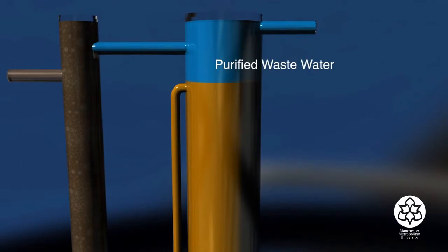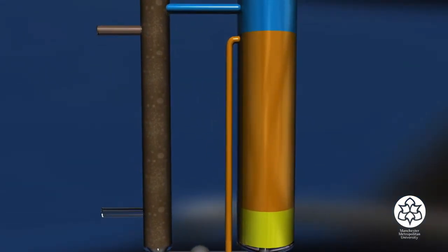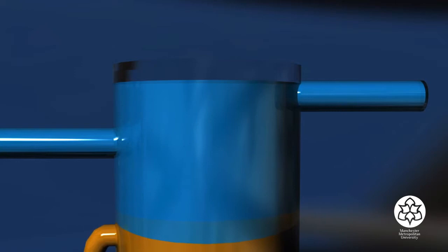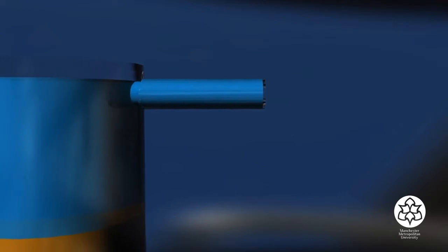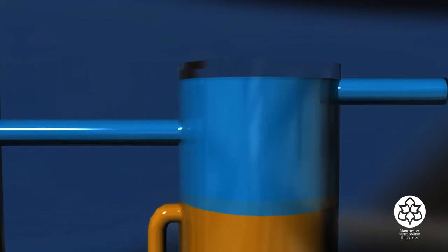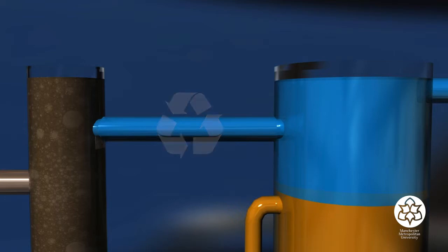purify the wastewater. As the bed expands, it continues to fill an increased volume of the expanded bed until it reaches the bioparticle overflow line, where it is drawn automatically back down to the base of the bed and is re-injected. Treated wastewater leaves the top of the bed and goes off to be discharged. Part of that wastewater may be recycled according to the particular flow characteristics of the works at the time. For example, if it's been raining heavily, we may have a single pass system, whereas in dry weather we would recycle at least 3 times through the system.